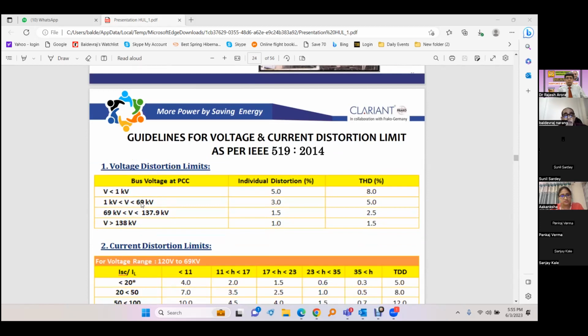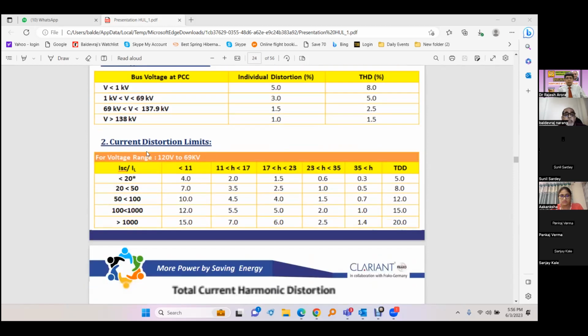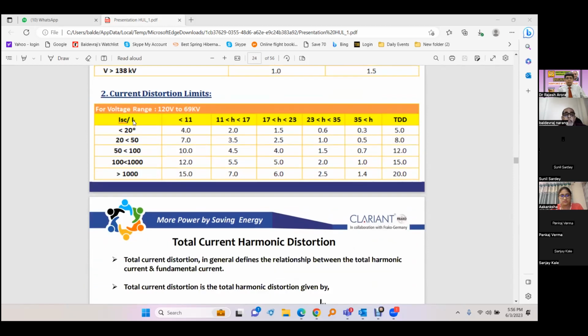Normally, most of the consumers are connected at up to 69 kV, and they have to maintain voltage harmonics at an individual level of 3% and THD of 5%. And for the current harmonics, mostly we have ISC by IL between 20 and 50, and we have to maintain TDD of 8%. Here we don't talk of THD because THD is not an indication of the severity of the harmonics. We have to consider TDD.